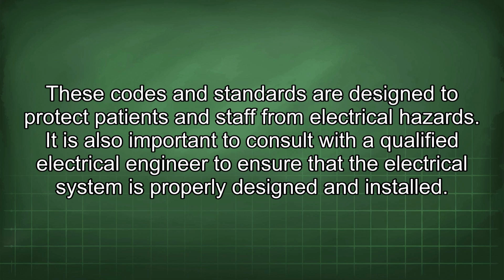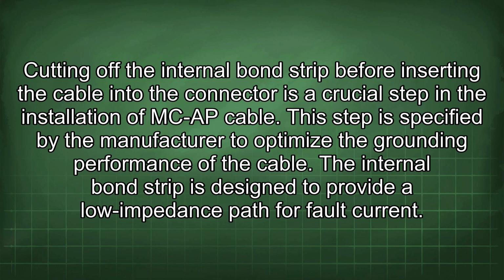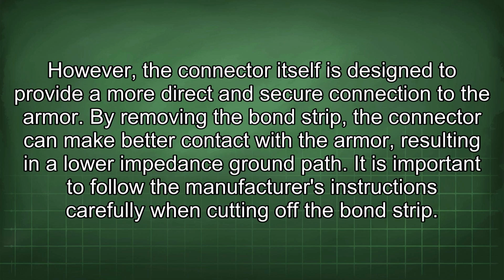and installed. Cutting off the internal bond strip before inserting the cable into the connector is a crucial step in the installation of MCAP cable. This step is specified by the manufacturer to optimize the grounding performance of the cable. The internal bond strip is designed to provide a low impedance path for fault current. However, the connector itself is designed to provide a more direct and secure connection to the armor.